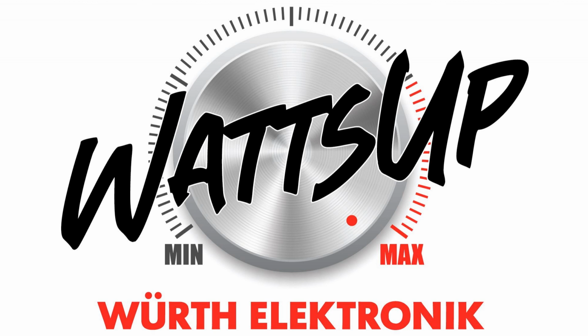So all these, in this case, we're below our limits. This is the peak, the quasi-peak limit, and this is the average limit. But yeah, it's always nice to have a little bit more margin. So that was the conducted emissions.